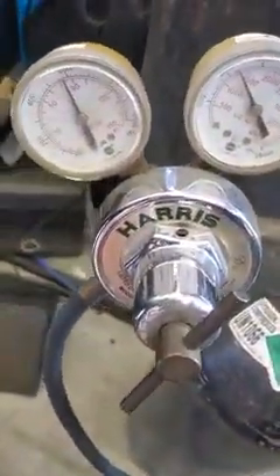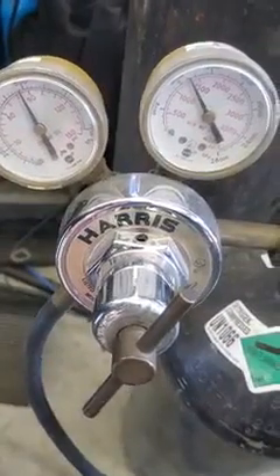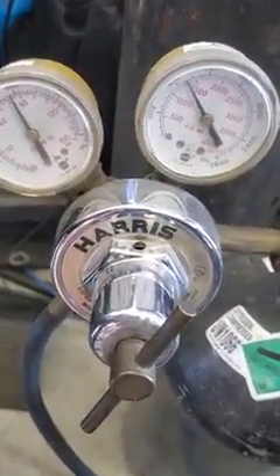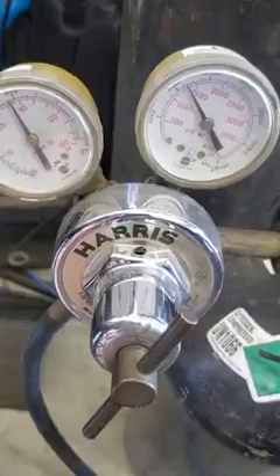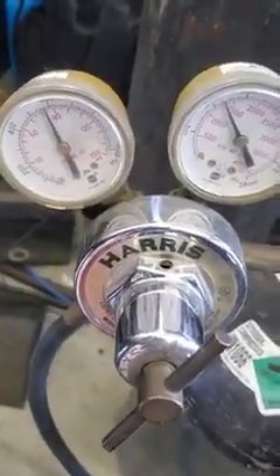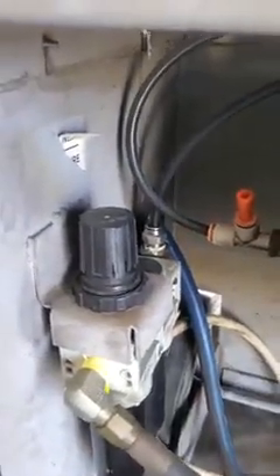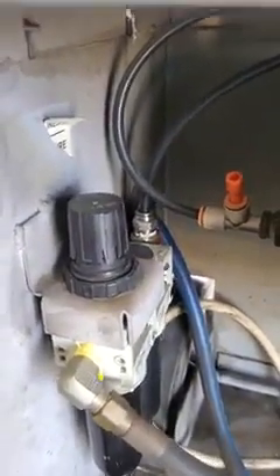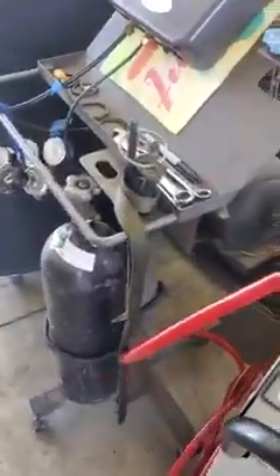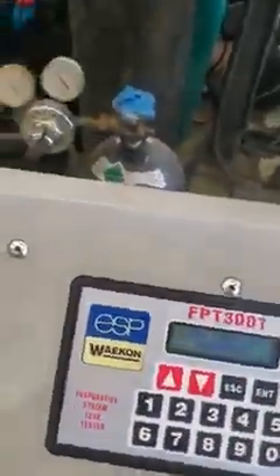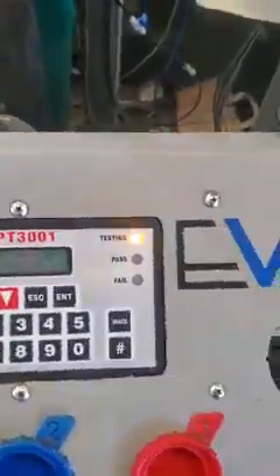Your bottle regulators, the gauge on the right shows that you have pressure in the bottle. The gauge on the left should be set to 80. Anywhere from 70 to 90 would be fine. There is another smaller, more precise regulator in the cabinet. This is the one you will set to 32 psi in the machine if needed.